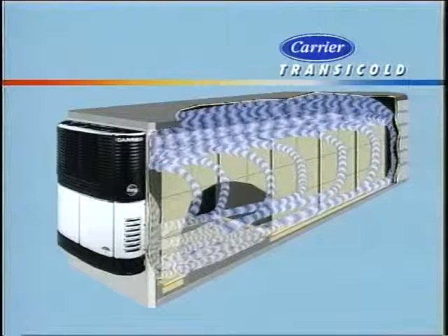The switch moves from side to side. Toward the trailer is the glow position, and away from the trailer is crank. Hold the switch in the glow position, then turn the start on-off switch to the start run position to preheat the engine. When the display powers up, manual start mode selected appears in the message center.